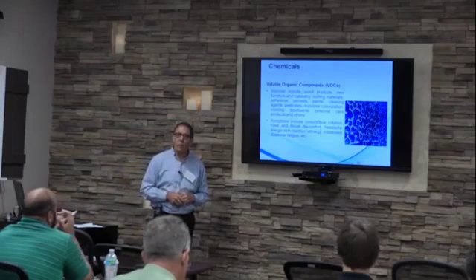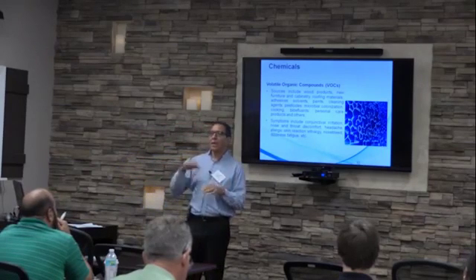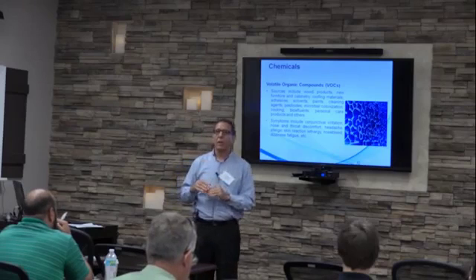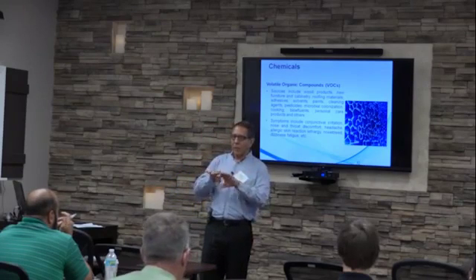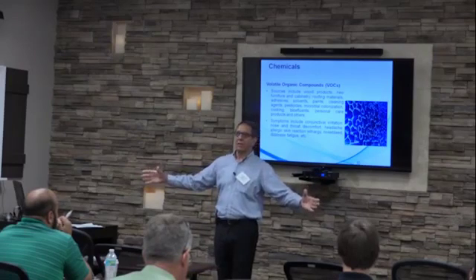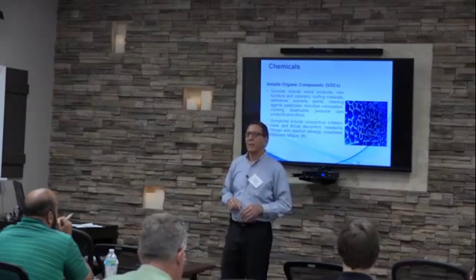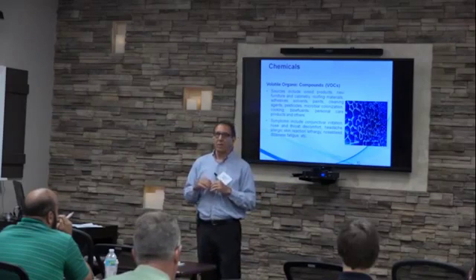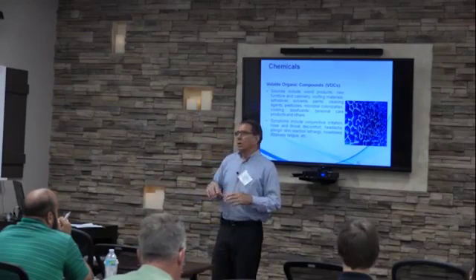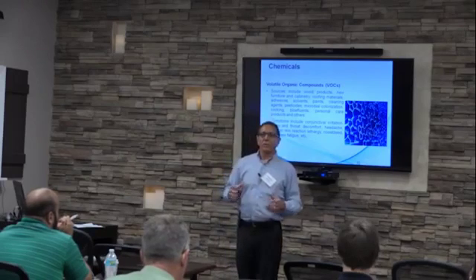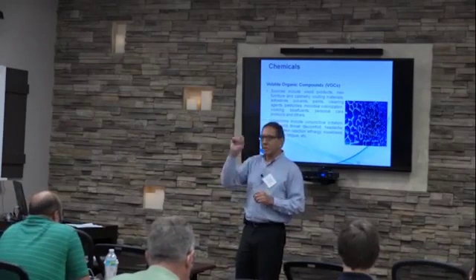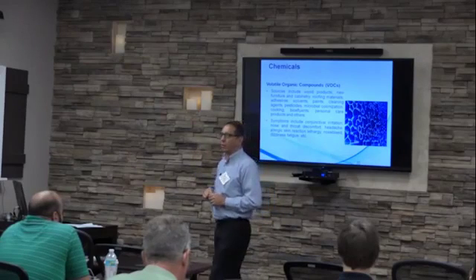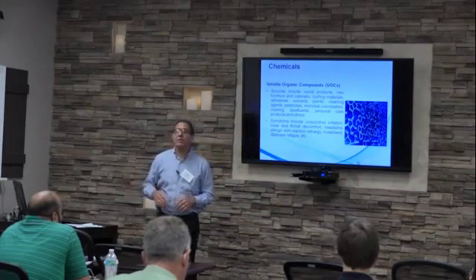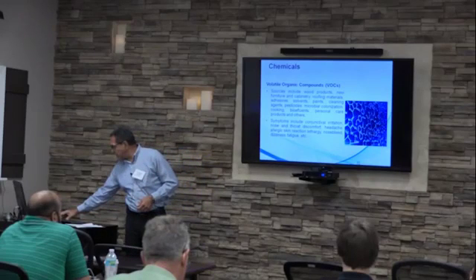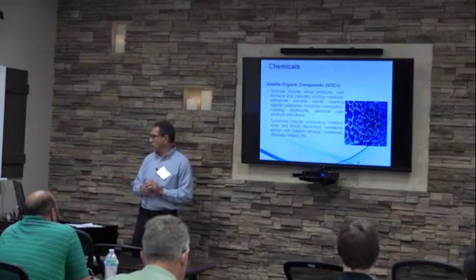We have seen several situations with that, one recently was quite interesting. We modified the ventilation system, closed off the exhaust, and rerouted the fresh air intakes away from the roofing that was being replaced. We also turned the building into positive pressure temporarily so the vapors generated by the roofing materials would not infiltrate through the small crevices and holes present in the roofing deck. That made a big difference, and we were able to complete the project successfully.